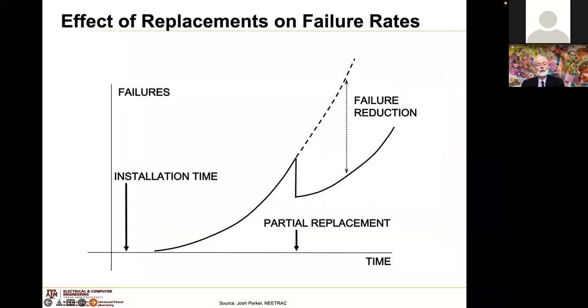So what we are trying to associate with all of them is a moment of installation, and then a time during which the number of failures in such a system are growing. So let's say we install at year 100 miles of cable. In different segments of that cable, we will be experiencing failures over time, and they will be growing up to a point of partial replacement, when hopefully the new cable that is replacing an old one causes a reduction in failures.